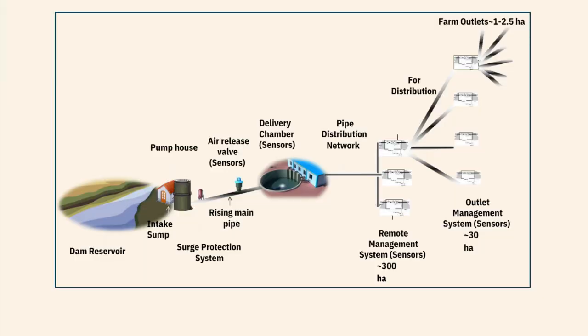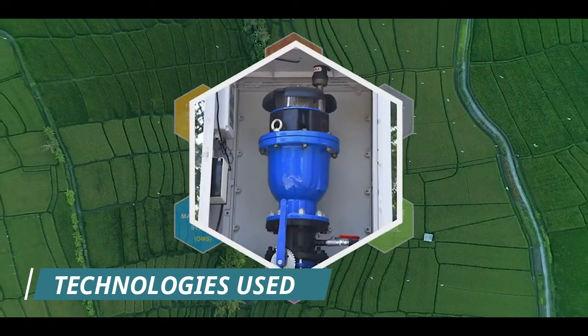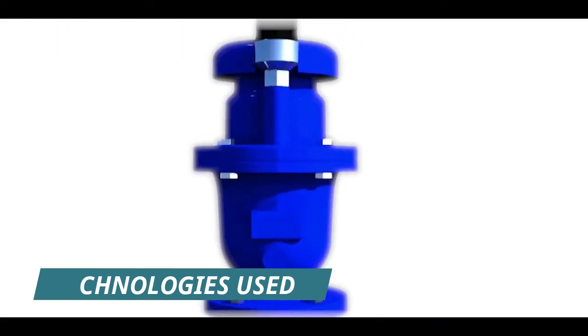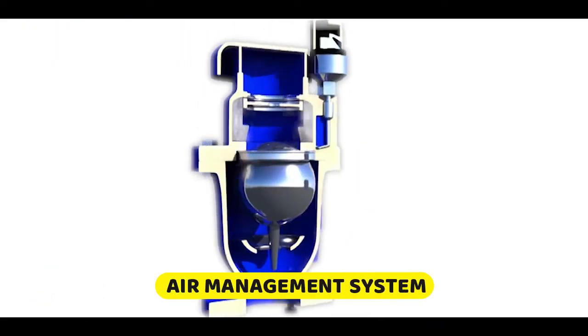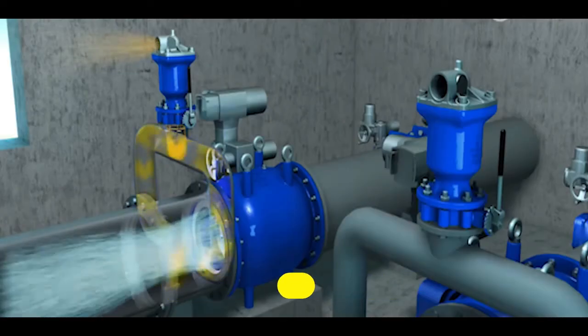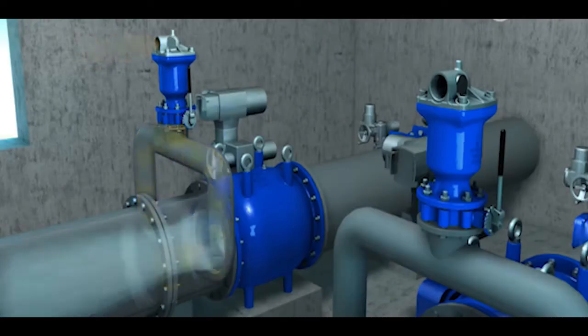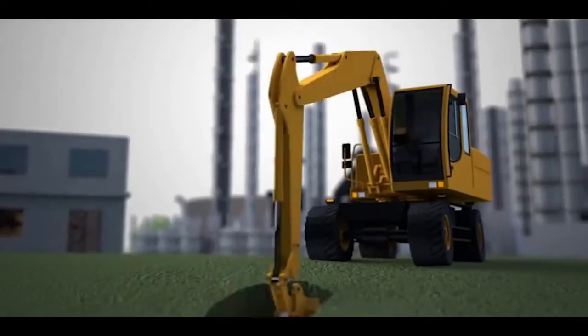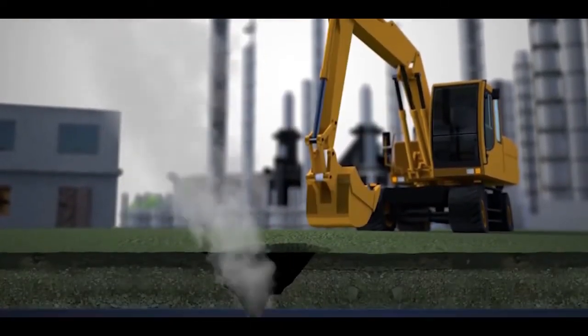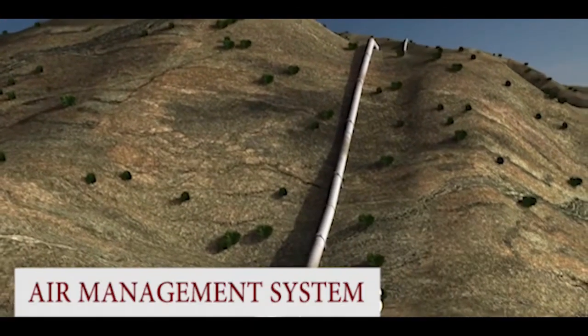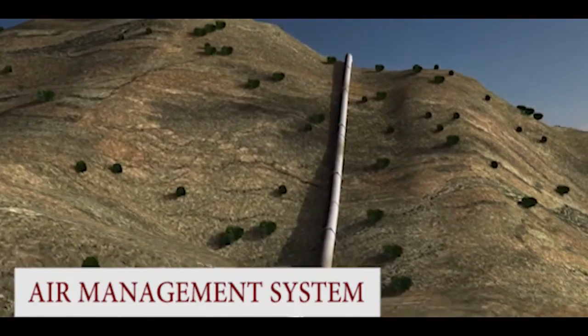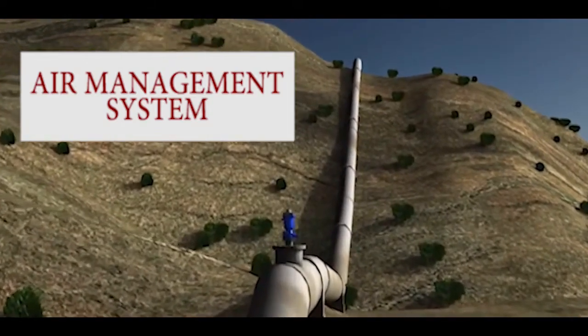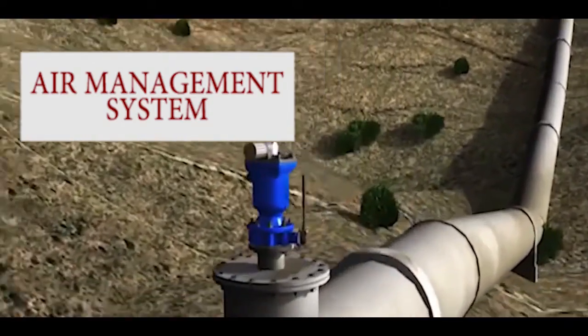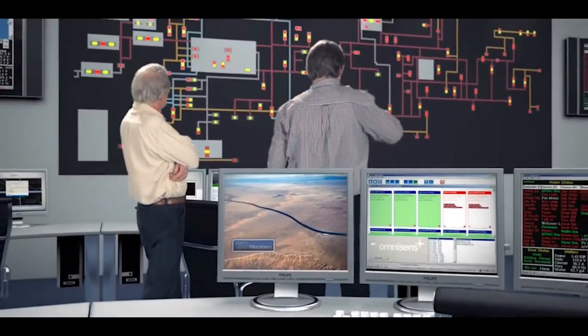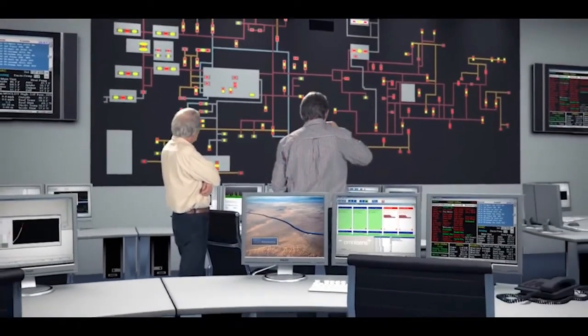The SCADA system is divided into 2 parts: the pump house SCADA and the field SCADA. It would be designed with the currently available best ARI system, which will prevent damage to the pipelines caused due to air gaps generated at the time of water flow or its stoppage in different pipelines, and will identify leakages at different locations. Problem-free operation of the scheme will be ensured by using the Air Management System at regular intervals, for which it is equipped with a smart solution, and the scheme will be constantly monitored by the SCADA system.